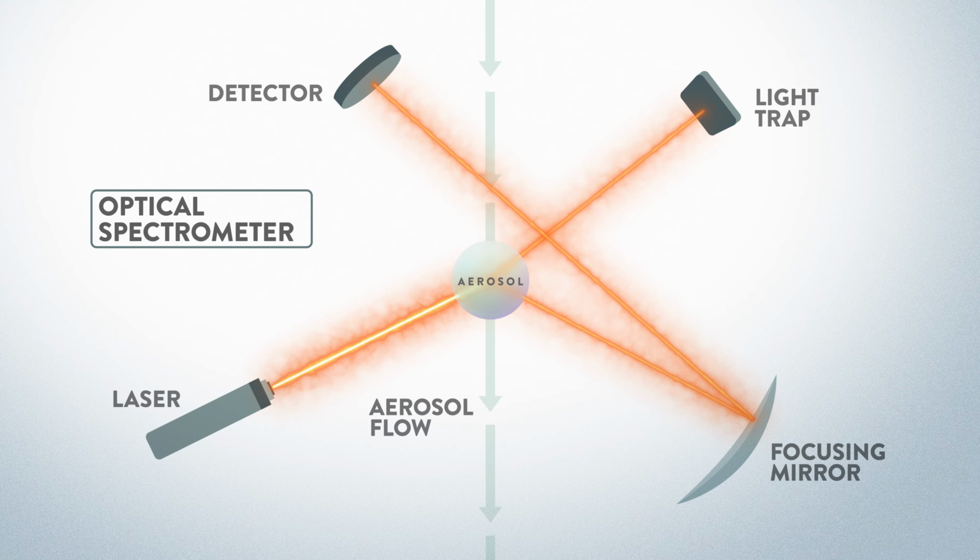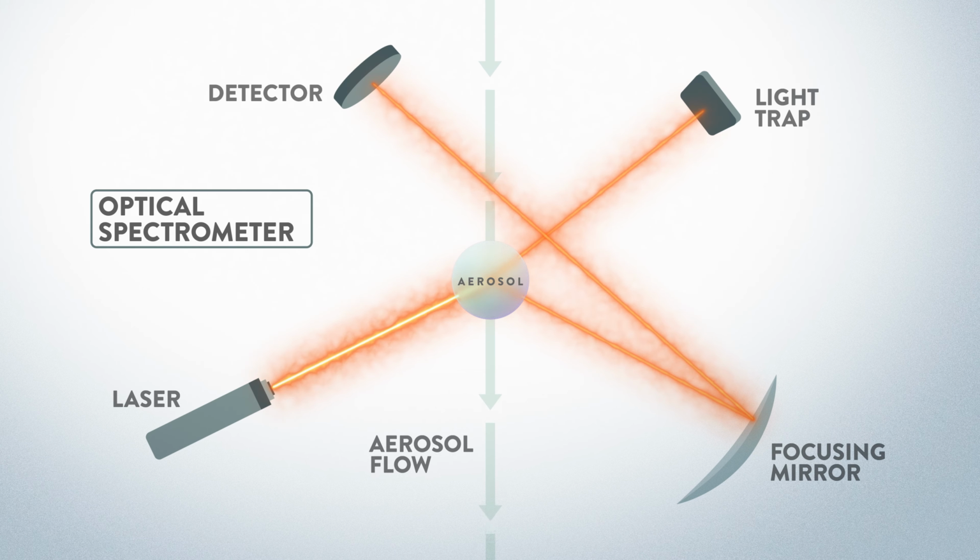When using an optical spectrometer, the sample air is led directly into the measuring cell via the aerosol inlet. The particles in the sample air are detected by light scattering inside the measuring cell. The scattering light pulse of every single particle is counted, and the intensity of its scattering light signal is classified to a certain particle size.